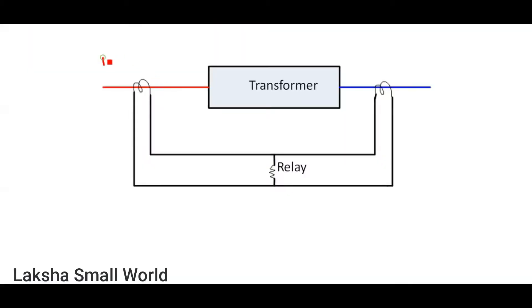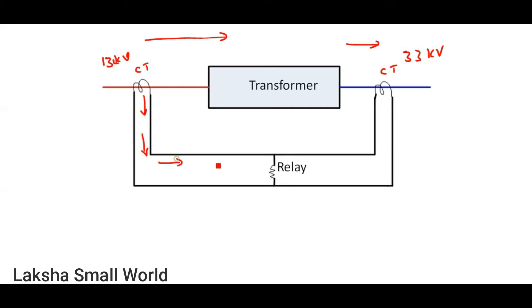So this is the 132 kV side and this is the 33 kV side. The transformer is connected to the 132 kV supply, and there is one CT on each side. Normally power current flows through the CTs in a certain direction. When current flows in through both CTs in the normal direction, inside the relay almost no current will flow because the two currents are almost equal — the difference in current is zero, so the relay will not operate.